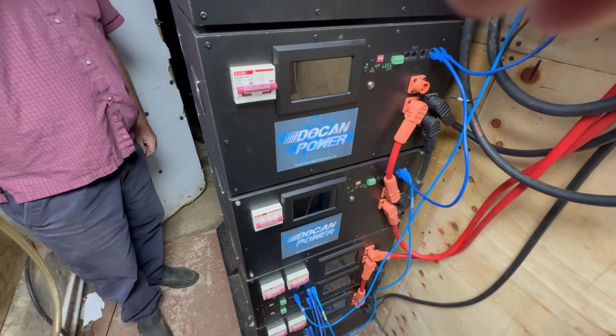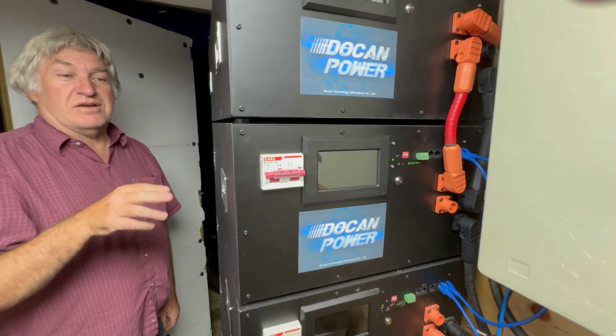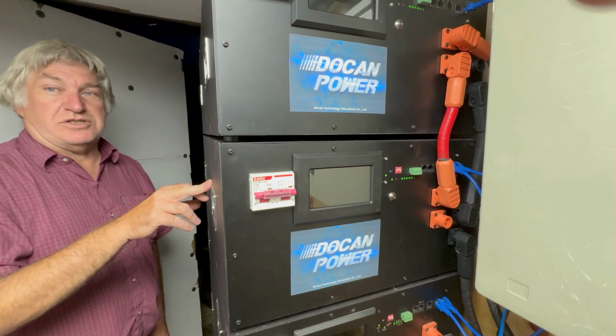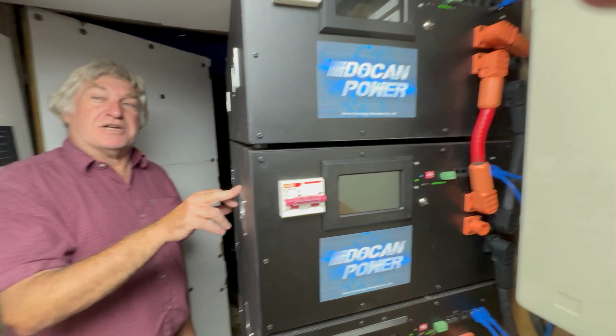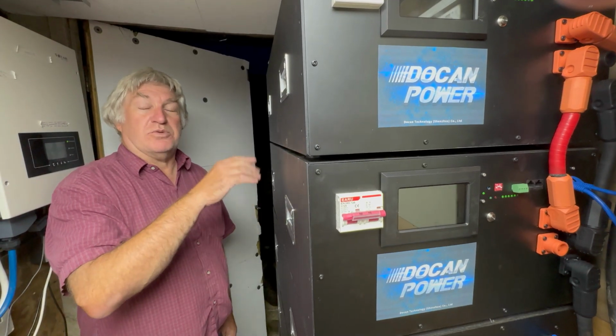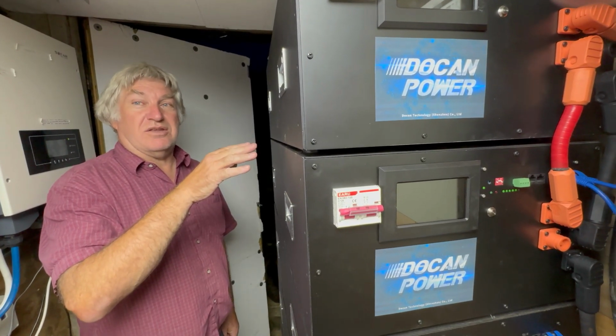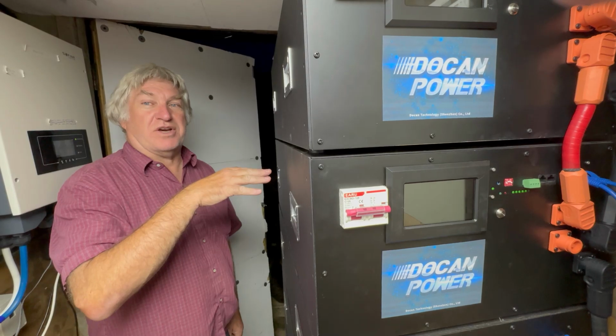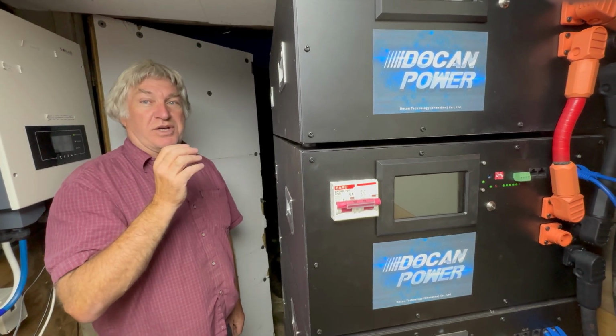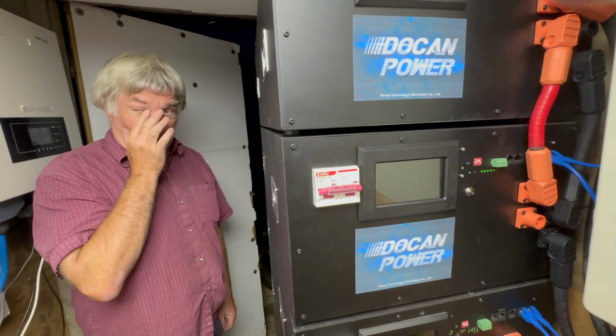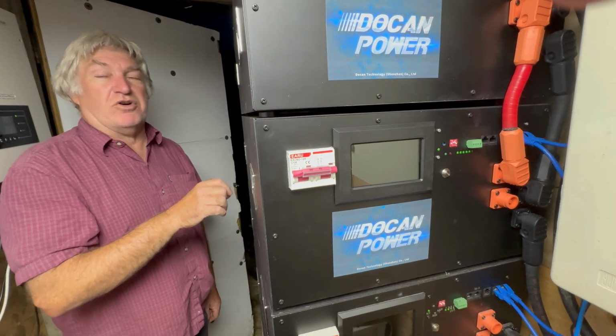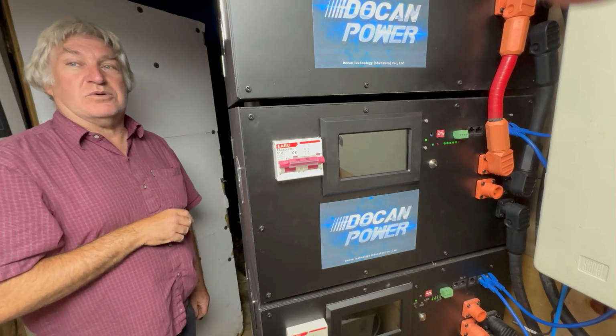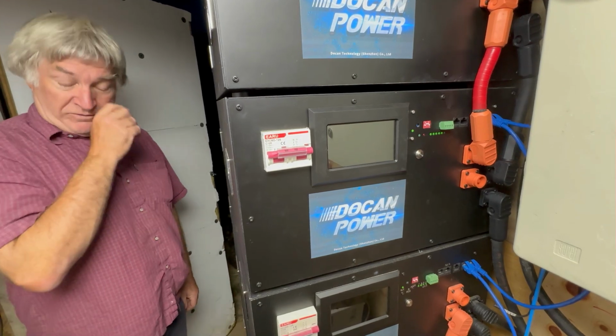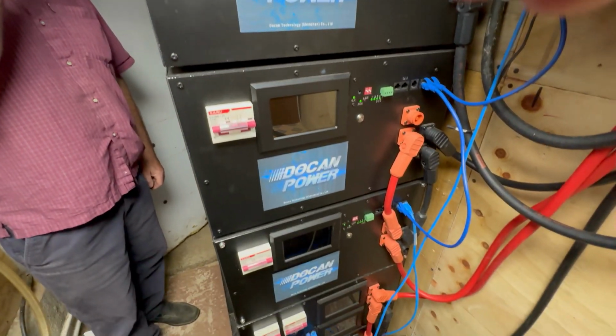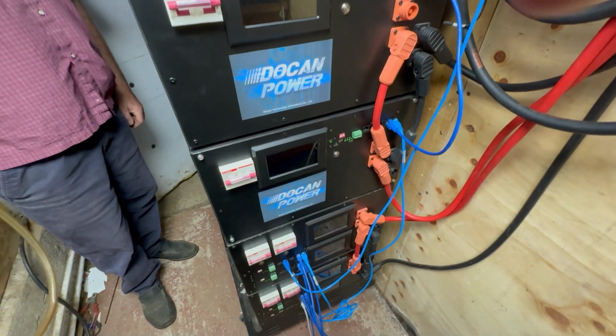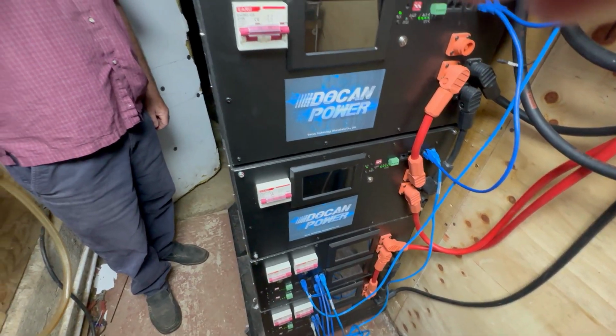The advantage over the lead acid batteries is these will absorb as much energy as you can throw at them. The lead acid batteries, as they came up near the top of charge, would drop to a much lower charge rate, and you'd start throwing solar energy away. These will keep swallowing as much current as you can give them, right up to the last couple of percent of charge, so they take everything the solar system can generate and soak it all up, and we don't have to export anything to the grid.